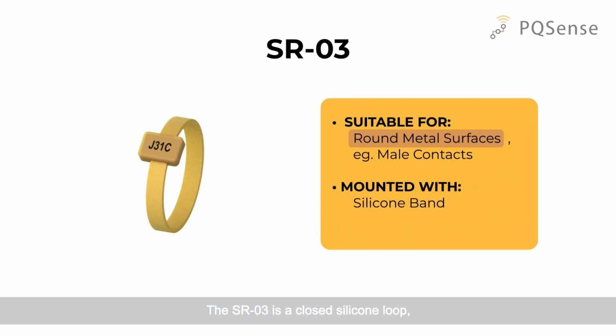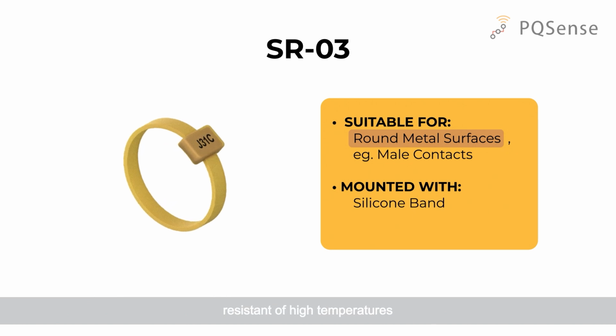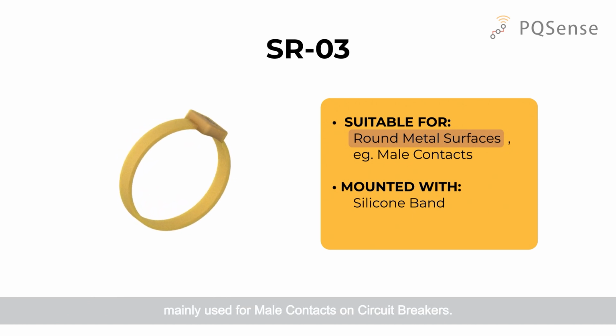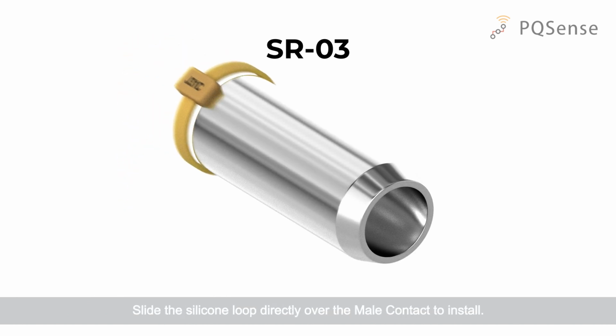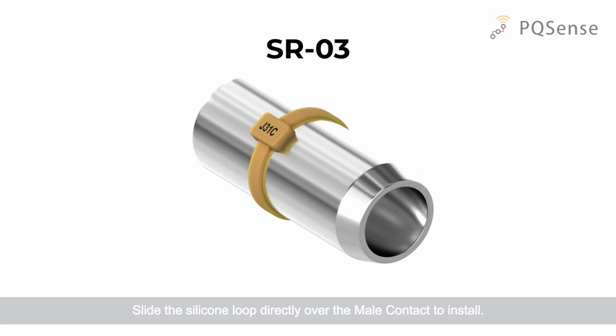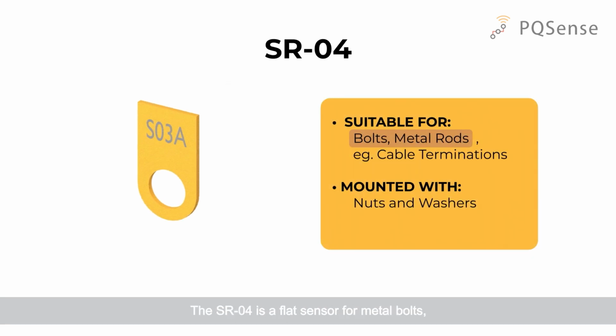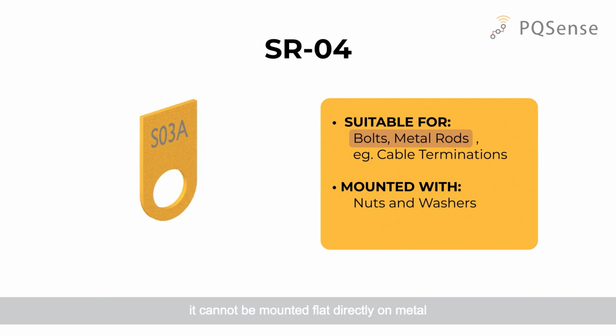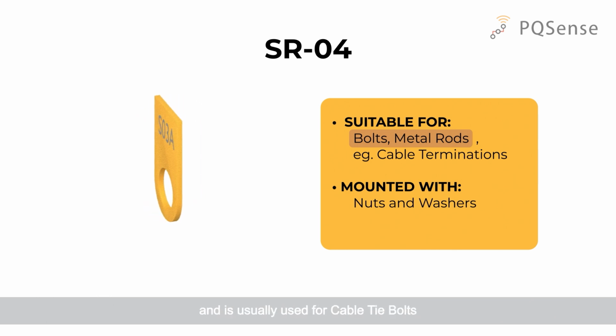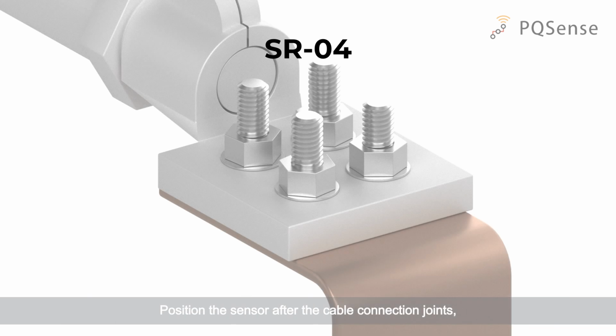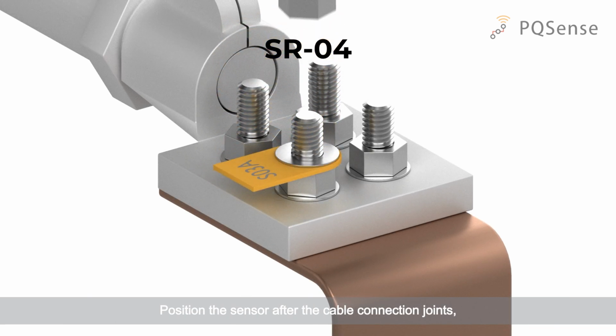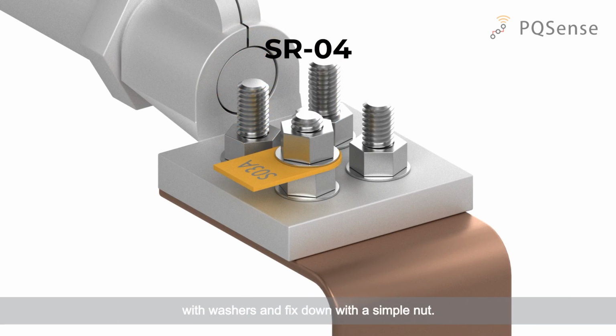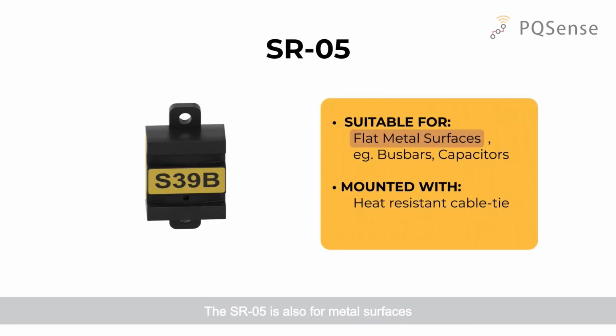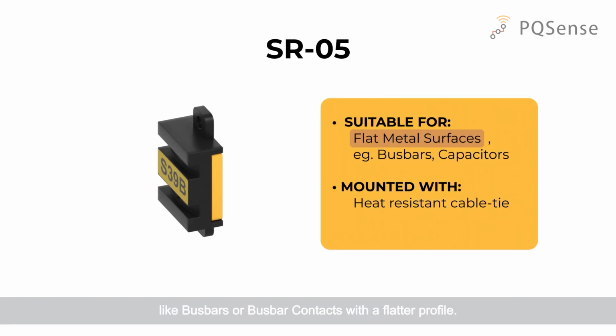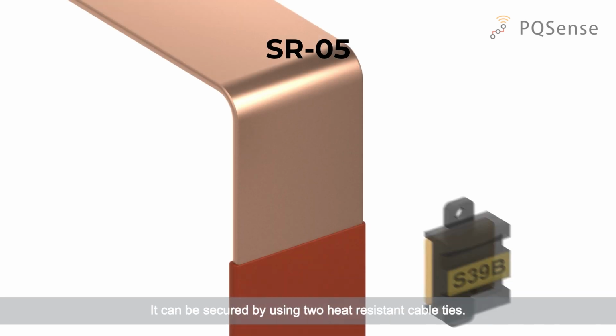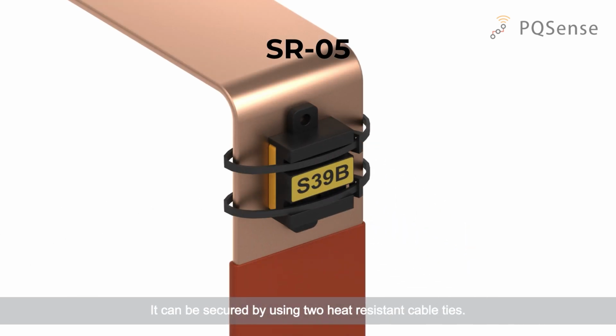The SR03 is a closed silicone loop, resistant to high temperatures, mainly used for male contacts on circuit breakers. Slide the silicone loop directly over the male contact to install. The SR04 is a flat sensor for metal bolts. It cannot be mounted flat directly on metal and is usually used for cable tie bolts. Position the sensor after the cable connection joints with washers and fix down with a simple nut. The SR05 is also for metal surfaces like bus bars or bus bar contacts with a flatter profile. It can be secured by using 2 heat-resistant cable ties.